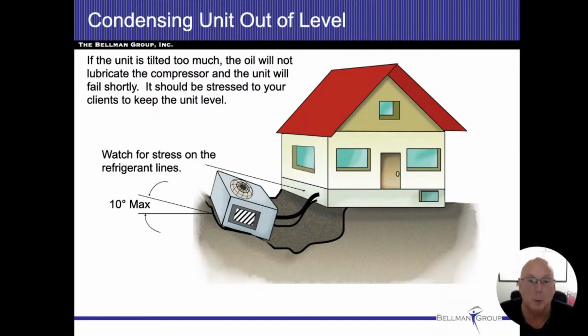And the compressor is the most important part because it's the only moving part, so it's also the most expensive part, and that's the one that we want to protect, all right? So keeping it level is a good thing. However, air conditioning systems today are dealing with scroll compressors, and they don't have a tray of oil underneath them to keep them lubricated. The oil and the lubrication that they're using is actually inside the refrigerant itself. So as long as that refrigerant is moving freely, then everything's going to stay lubricated.